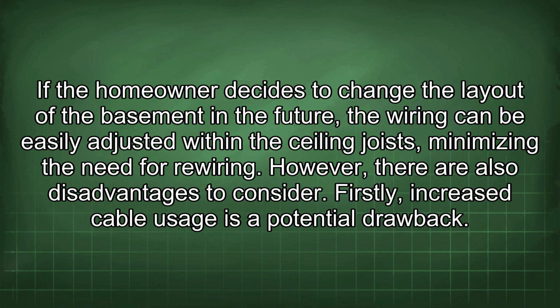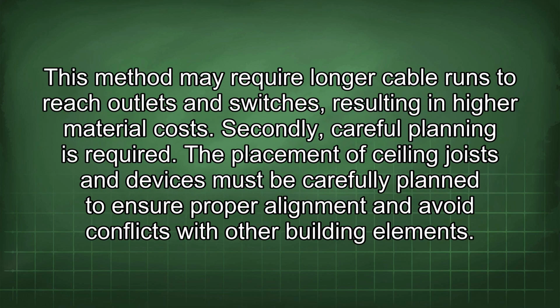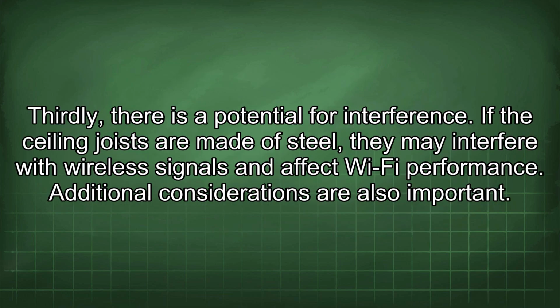However, there are also disadvantages to consider. Firstly, increased cable usage is a potential drawback. This method may require longer cable runs to reach outlets and switches, resulting in higher material costs. Secondly, careful planning is required. The placement of ceiling joists and devices must be carefully planned to ensure proper alignment and avoid conflicts with other building elements. Thirdly, there is a potential for interference. If the ceiling joists are made of steel, they may interfere with wireless signals and affect Wi-Fi performance.